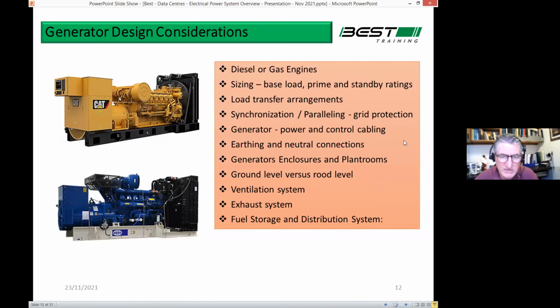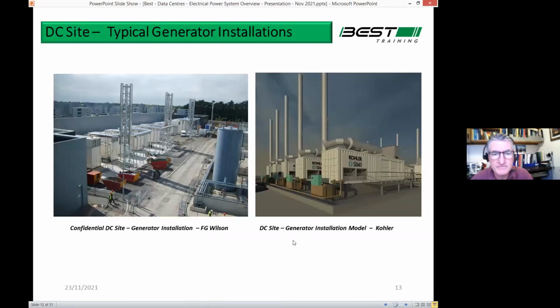So it can be bulk stored in a central tank, like in a tank farm, and pumped around, which is rarely done, and not recommended, obviously, because the whole distribution system becomes a single point of failure. So the alternative is that now they're building them with each generator having a tank underneath, a base tank. They're called in the industry belly tanks, but it's basically just a big base tank sitting here, and the generator draws the fuel directly off the tank below it. In fact, the image on the left is an actual confidential DC site. It's so confidential, I actually don't know myself which one it was. Somebody shared the picture with me.